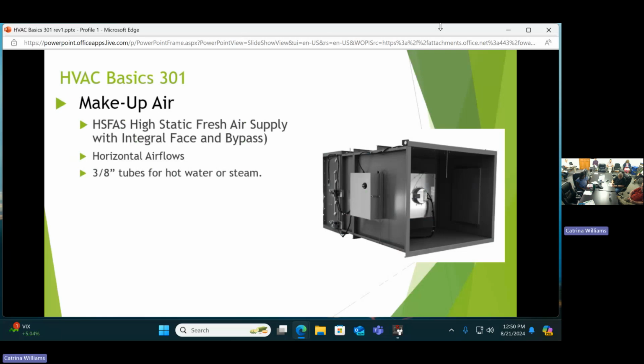3/8 tubes for hot water or steam. But now we're using an electronically commutated EC motor with a direct drive plenum fan to handle higher pressure. That motor is an electronic motor, very high efficiency. You can program it to do various things. You can set it for a constant CFM. For example, if your filters start loading up and blocking part of your airflow, it'll compensate for that to some extent and keep it constant volume all the time. And it can also handle the higher statics that they're concerned about.